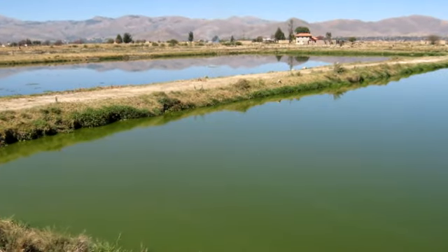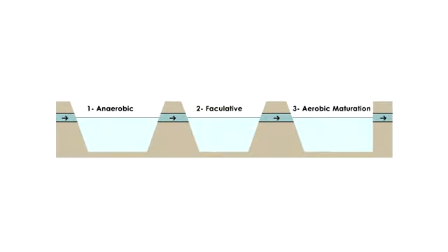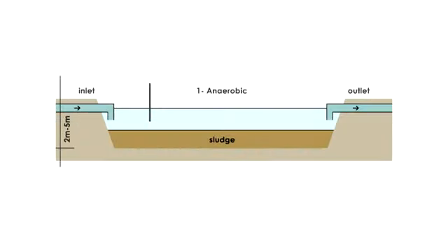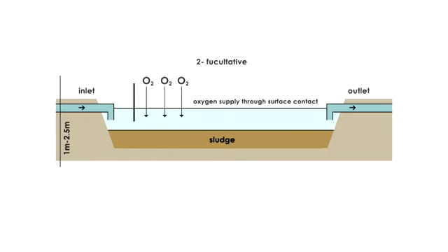Wastewater stabilization ponds are open ponds whose treatment function depends on sunlight, the microbial life, and the lower forms of plants and animals. Organic matter is decomposed naturally. With the contribution of bacteria and algae, wastewater is stabilized and its pathogens are reduced. Generally, organic content of the effluent is converted to more stable forms. Stabilization ponds include various types such as sewage lagoons and oxidation, redox, maturation, facultative, anaerobic, aerobic, and aerated ponds. They can be used in a wide range of weather conditions alone, in series of various pond types, or in combination with other wastewater treatment systems.